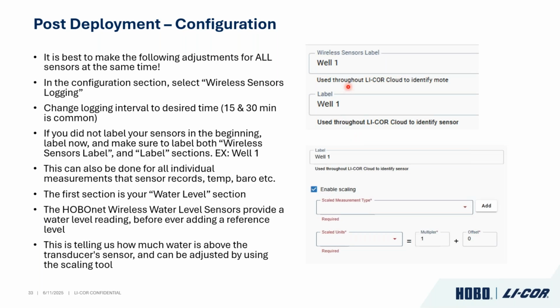At this point, I would change it. We know the network's stable, things are coming in — I don't want a data point every 5 minutes. Some common intervals are 15 minutes, 30 minutes, at least for water level, or even an hour. You can change that now so you're not collecting too much data. If you didn't label your sensors, you'll want to label them at this point.